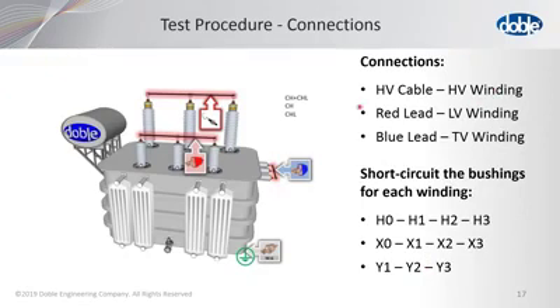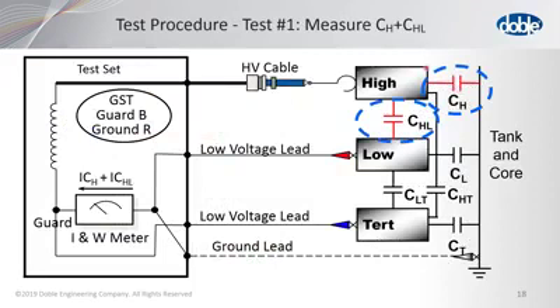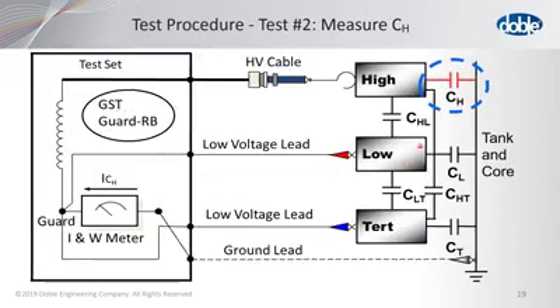And then inside DTA, we indicate where the high voltage, the red, and the blue low voltage leads are connected. And notice the high is on the high voltage winding here, the red is on the low, and blue is on the tertiary. And this is the first two-winding transformer that we're going to test. So here is the first two-winding transformer. We're energizing the high, and we're measuring both low and ground. We get CH plus CHL. That's test number 1.